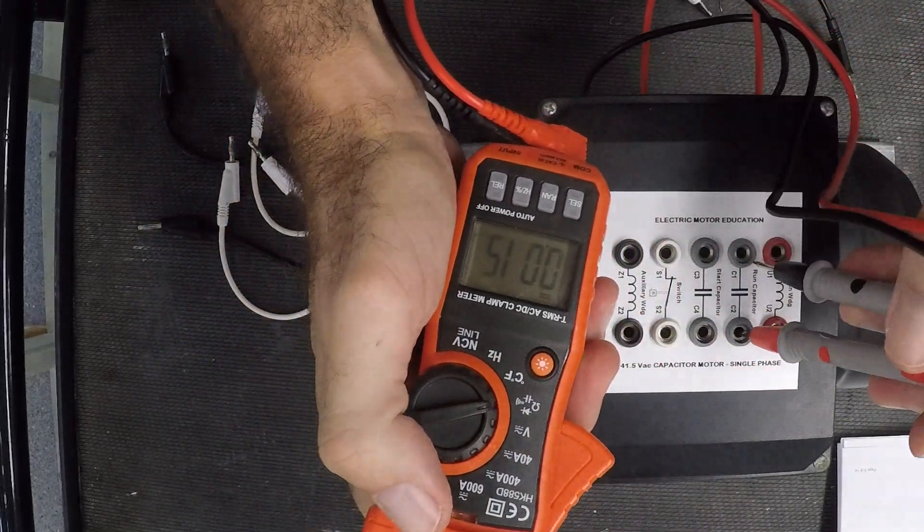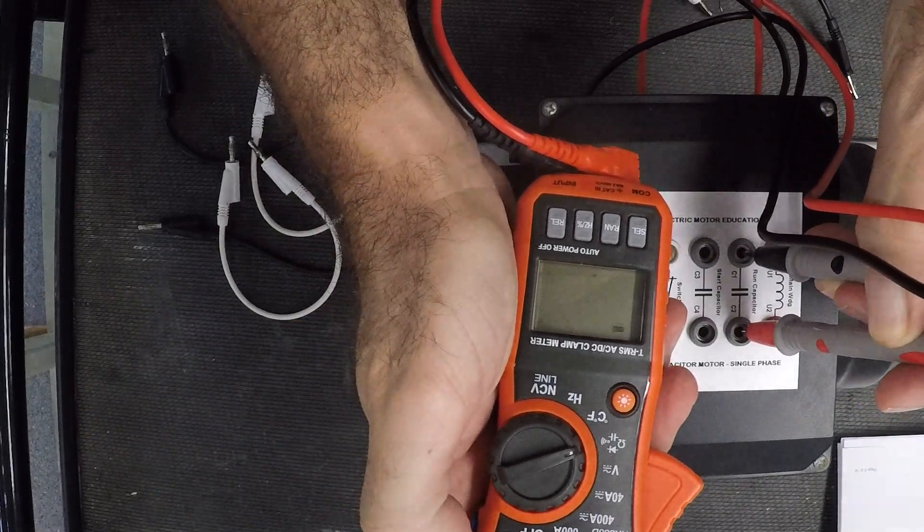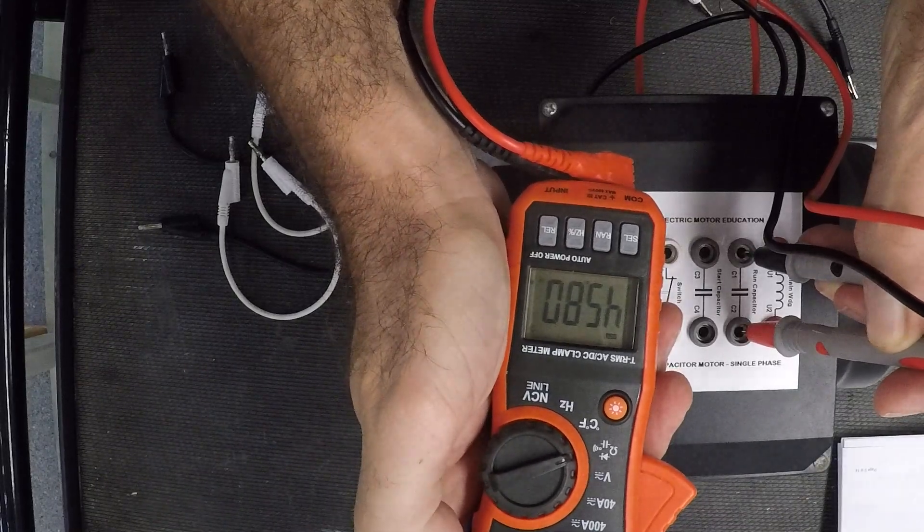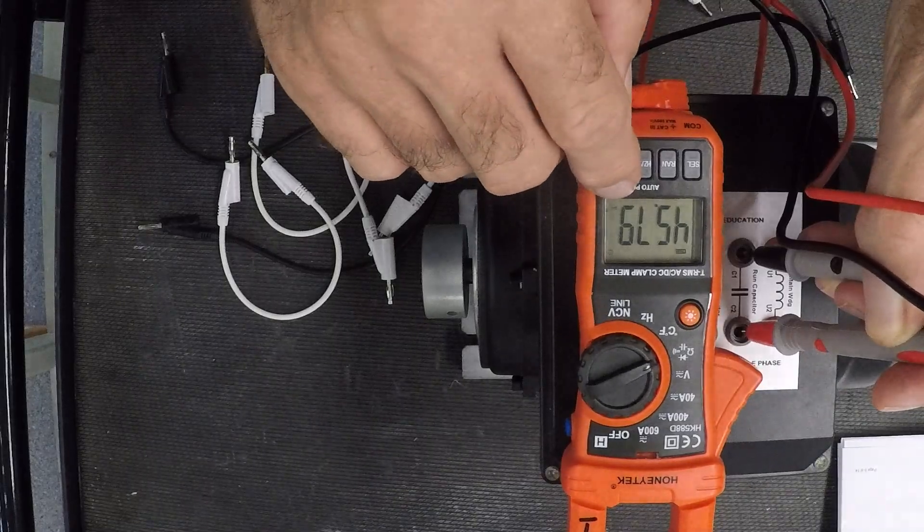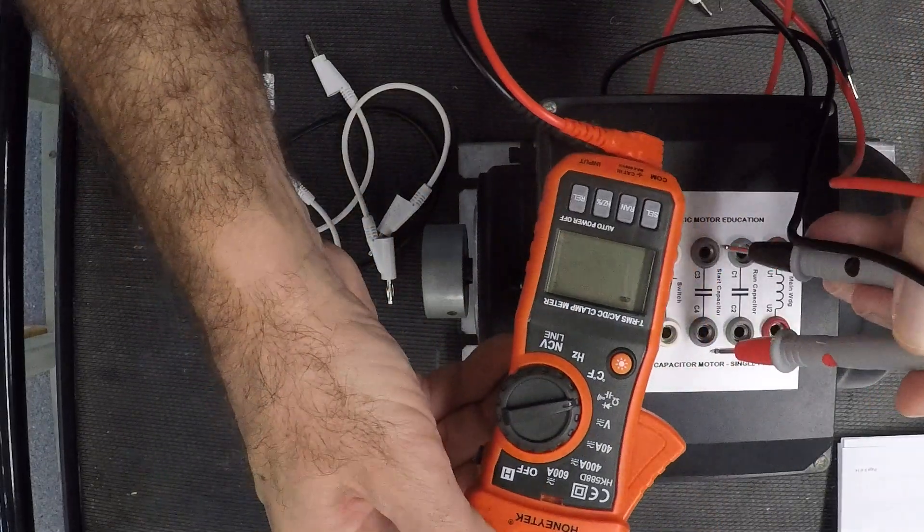So let's do the run capacitor. Now you've got to keep it there for a little while—it takes some time. I get 45.8 microfarad. I'm not sure if you can see it in the video, but the little tiny readings say microfarad.